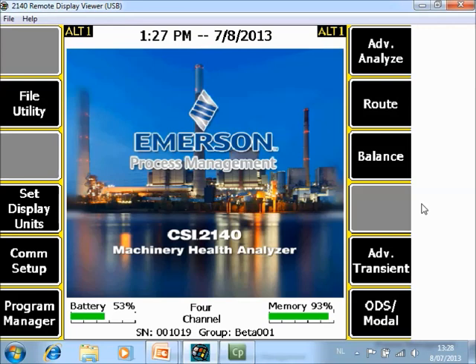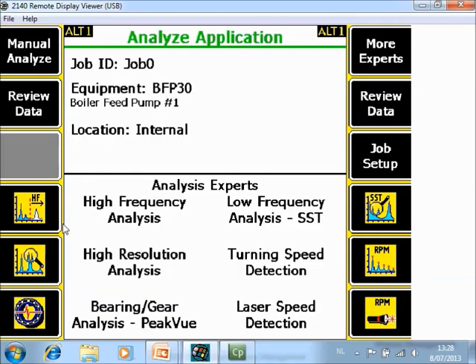What you are seeing now is the home screen of the CSI 2140 Machinery Health Analyzer. For the high frequency application, first go to Advanced Analyze F7. Here in the Analysis Experts, F4 High Frequency Analysis is pre-configured. I will now start the machine and we will start a measurement.